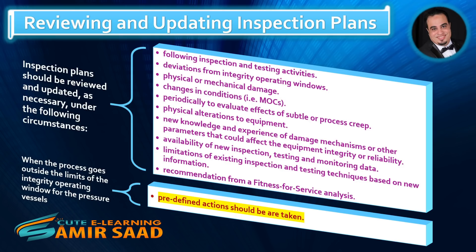Additional circumstances include: availability of new inspection, testing, and monitoring data; limitations of existing inspection and testing techniques based on new information; and recommendations from a fitness-for-service analysis. When the process goes outside the limits of the integrity operating window for the pressure vessels, pre-defined actions should be taken.